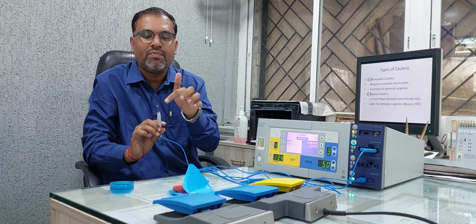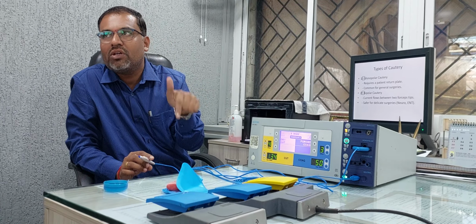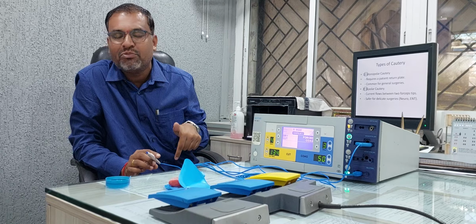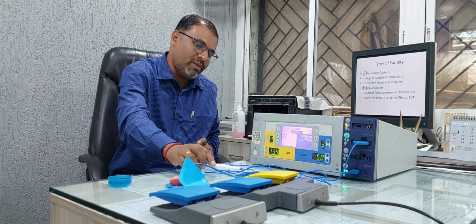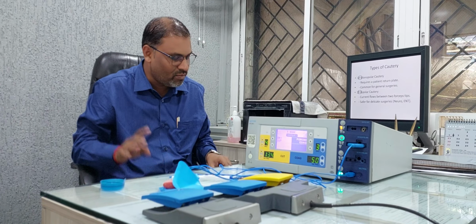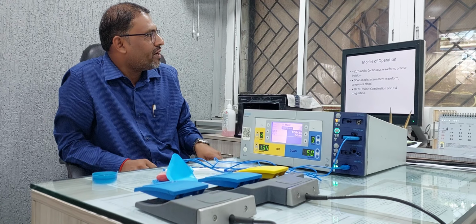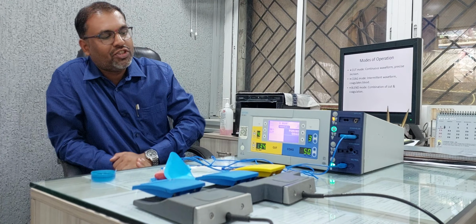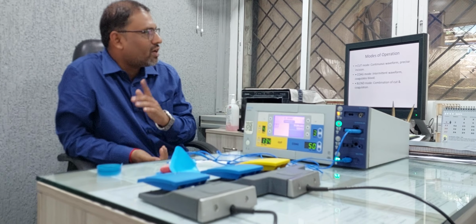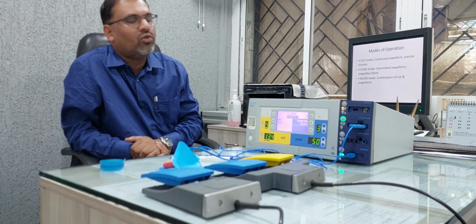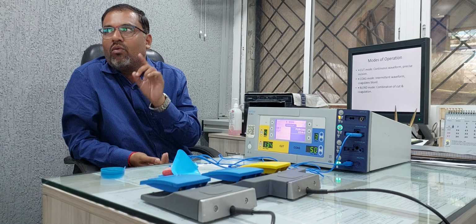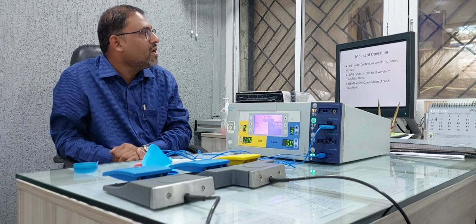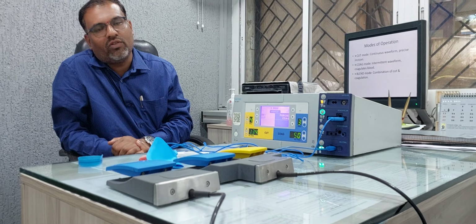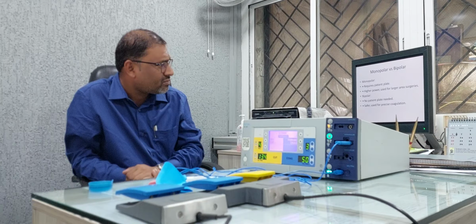So from this tip, current will be inside the body for the cutting and coagulation, and it has to be captured with the help of a patient plate. So this is a basic difference between monopolar and bipolar cautery. So what are the modes of operation in the cautery? First of all, your cut mode, second is your coag mode, and third is your blend mode. What is blend mode? In the same mode, you can use cut as well as coagulation. That's what is called a blending mode.